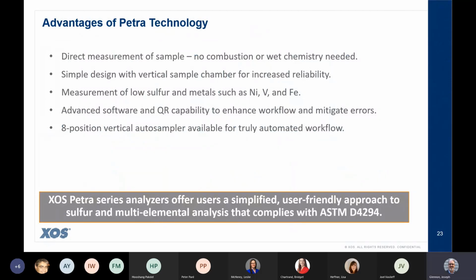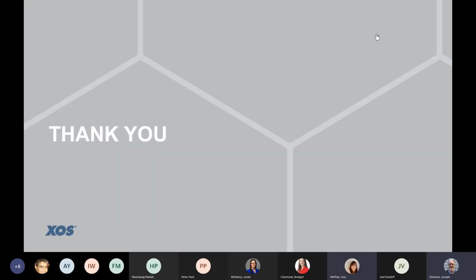So to sum it up, the advantages of Petra technology are direct measurement of the sample, no combustion or wet chemistry needed, and a very simple design with that vertical sample chamber for increased reliability. Measurement of low sulfur and metals on the Petra Max, such as nickel, vanadium, and iron. And that advanced software with the QR capability, enhancing workflow and mitigating errors. And the Autosampler, an 8-position Autosampler, which we are working on now, as you know, to re-release. So that's the presentation. Thank you to everyone for joining.